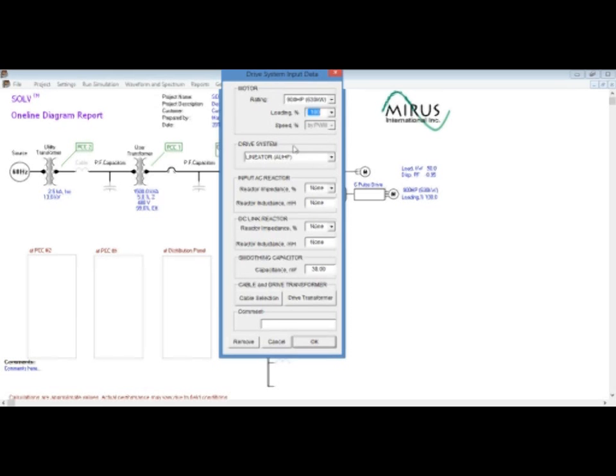In the drive system, we have choice of 7 different types of nonlinear VFD loads. Simple 6-pulse VFD, 6-pulse VFD with the lineator advanced universal harmonic filter, 3 types of multi-pulse VFDs, 12, 18, and 24 pulse, thyristor control DC drive, and DC drive with the lineator UHF. To demonstrate that the use of simple 6-pulse VFD will often result in harmonic distortion that will not meet recommended standards such as IEEE 519, our first simulation will be VFD only with the input AC reactor.